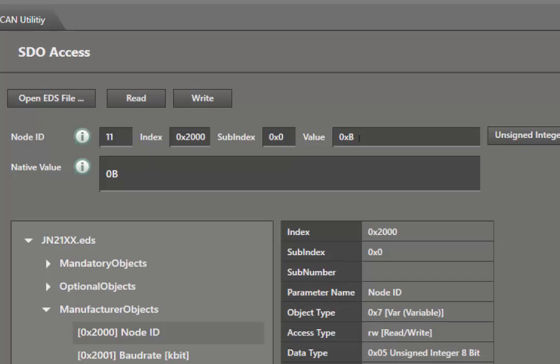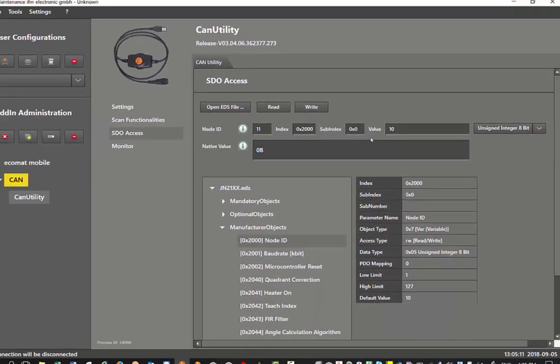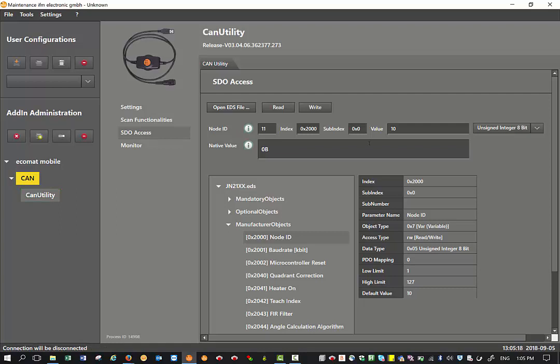Now say I want to change it to node ID 10 in decimal. I just delete in the value window and enter my value 10 and I write it now. It's been written successfully and if I want to make sure that I have written the value successfully, I just click on read and you can see the value has been changed. But this value will only take effect after you've done a power cycle on the respective CAN device.